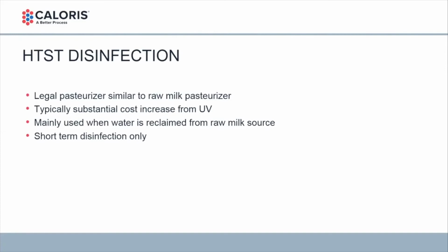And as I was saying, this is also short-term disinfection. So at the outlet of that pasteurizer, everything's going to be dead, but there are organics in the product. So any bugs that get downstream are going to start growing. So that's what I mean by short-term disinfection only, and you need to design it so you can take care of that issue.